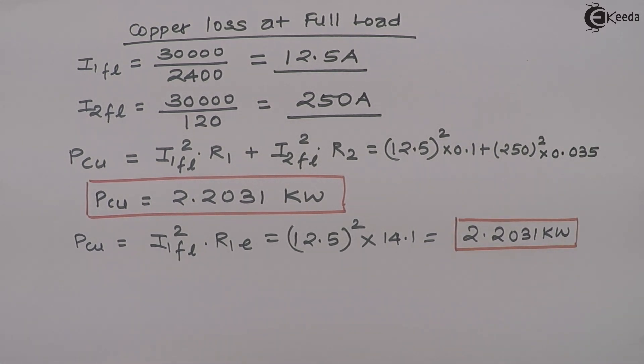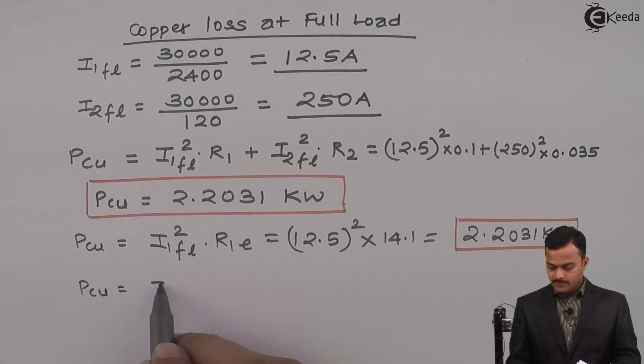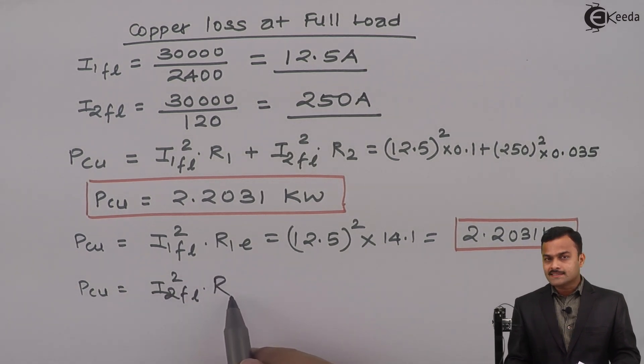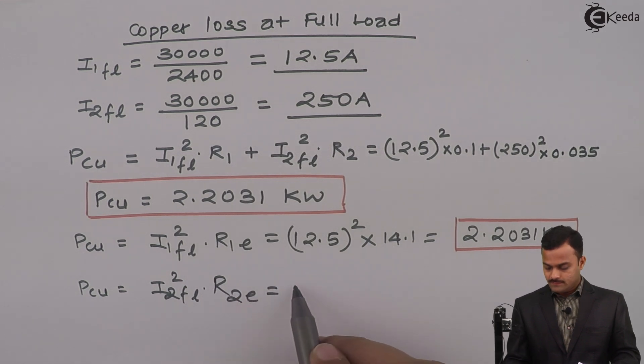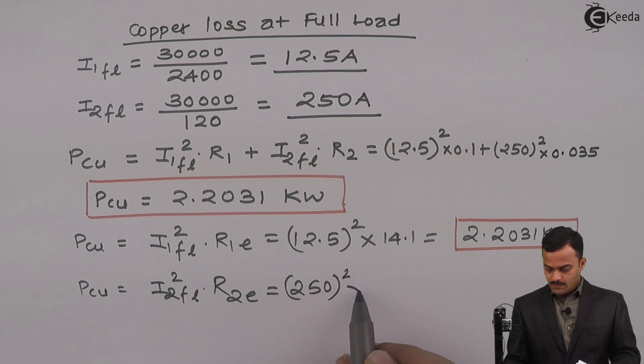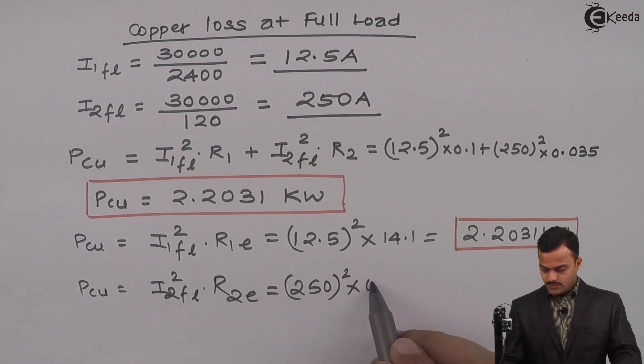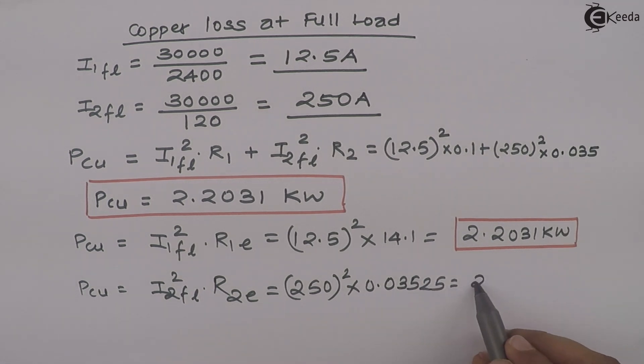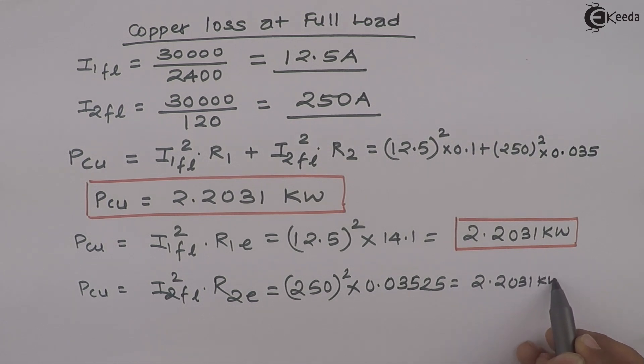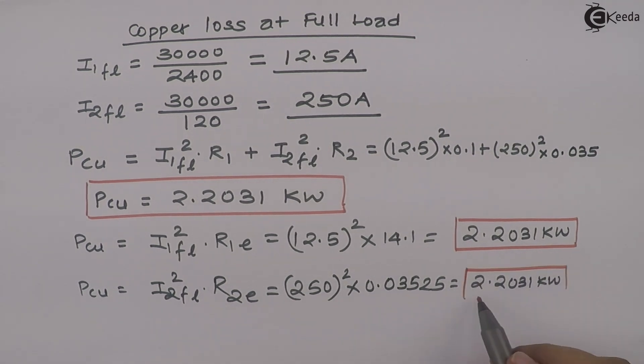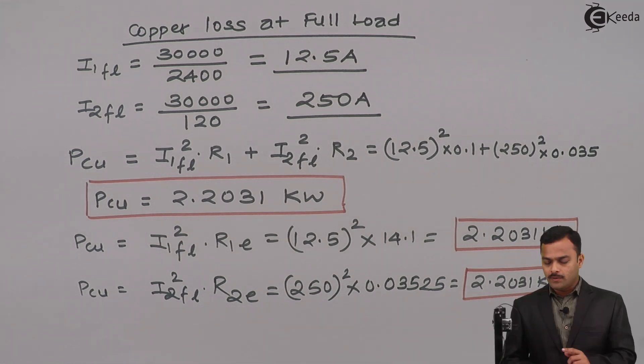Similarly, using the circuit referred to the secondary side: copper loss = I2FL² × R2E = 250² × 0.03525 = 2.2031 kilowatt — once again the same answer. Depending on whatever parameters are given, use the appropriate formula to get copper loss. Thank you.